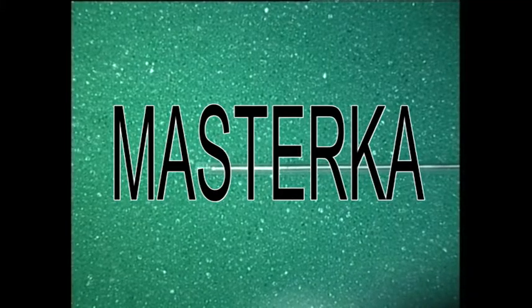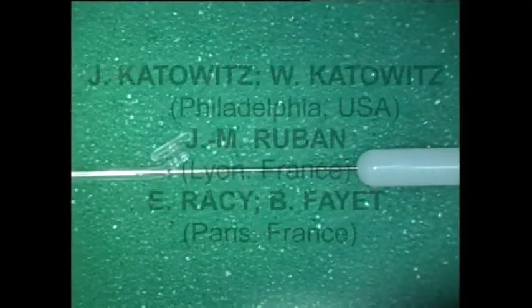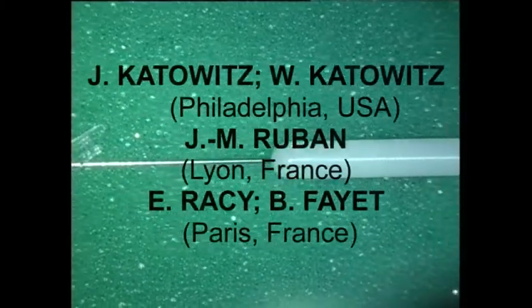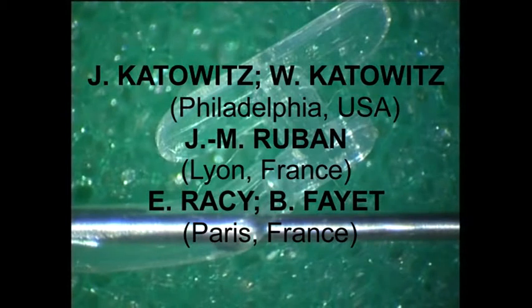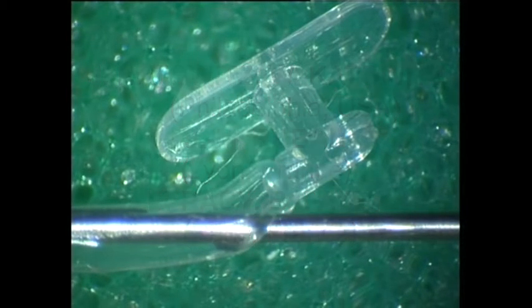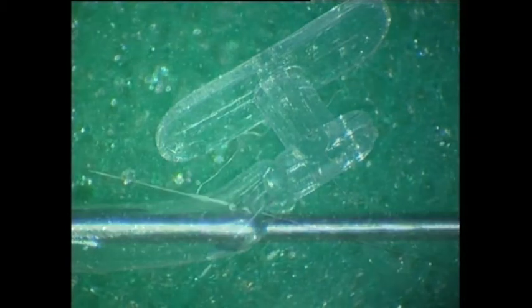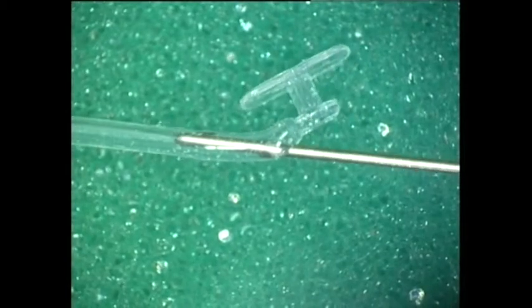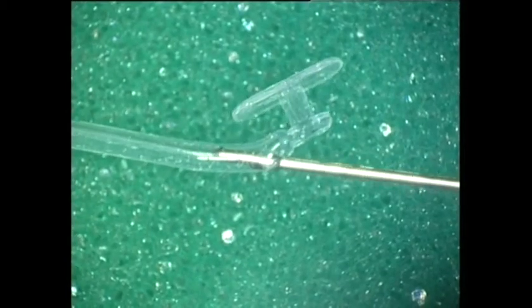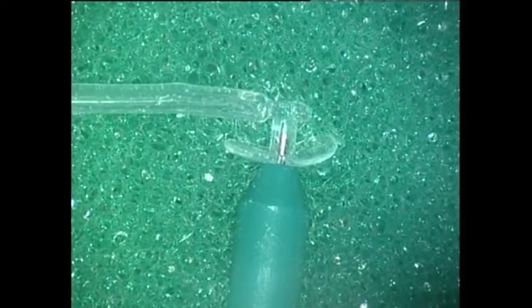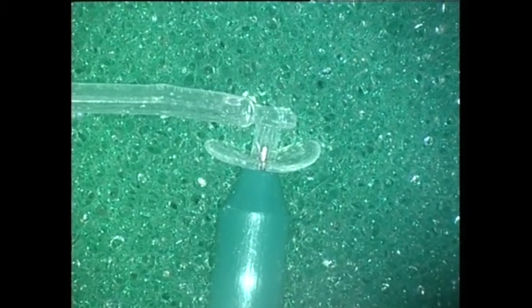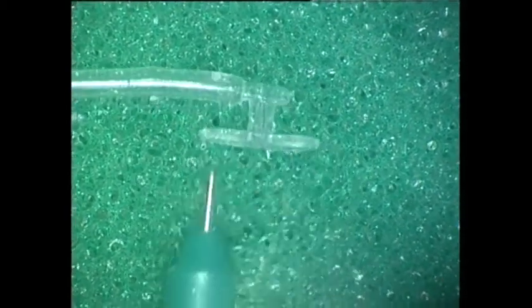The Masterka is a special type of Monoka stent that can be inserted by a pushed rather than a pulled technique. It is comprised of a silicone sleeve and fixation head identical to those of standard Monokas, but with a removable insertion guide placed inside the lumen of the silicone. The design of the Masterka follows the same insertion concept used for venous catheterization. The stents for the Masterka push type of nasolacrimal intubation come in three lengths: 30, 35, and 40 millimeters.